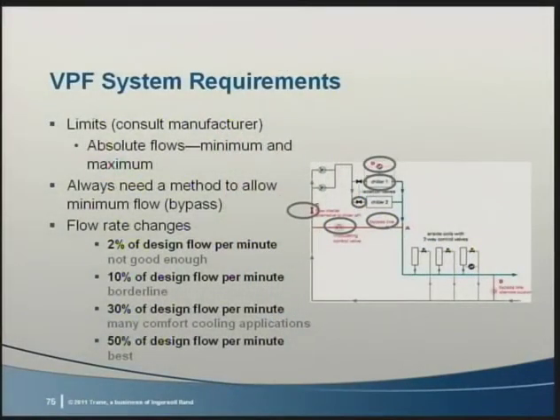In addition to chiller changes and design parameters, there may be times when changing the system configuration provides significant benefits. Many of the newer chiller controls allow variable evaporator flow. Let's examine the opportunity, discuss requirements, and look at ways that this can be used. We've covered variable primary flow systems in several E&Ls in the past. Here are 3 system issues that we've discussed before.